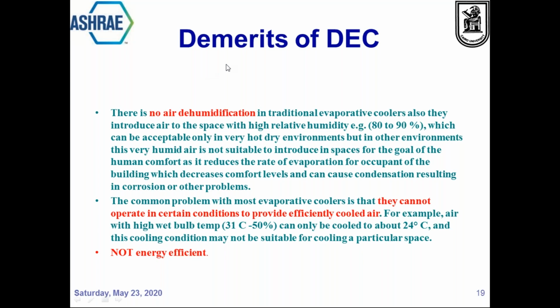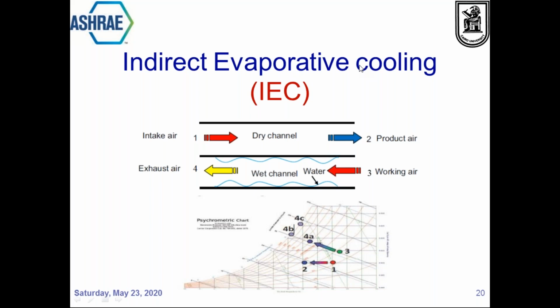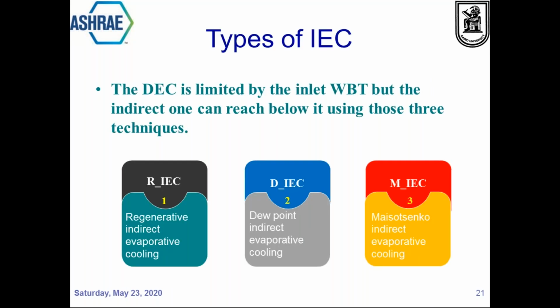So we have some disadvantages of direct evaporative cooling, and it is not energy efficient alone. So we think about indirect evaporative cooling, where we have a surface in between, so the streams are not directly connected to each other, and we have our air coming and being subjected to heat transfer, while the other stream takes heat from it. So for indirect evaporative cooling, we can have what we call regenerative, dew point, and also Maisotsenko indirect.